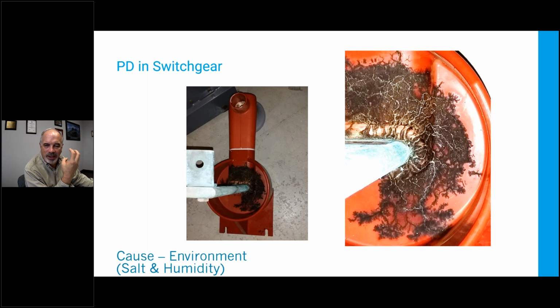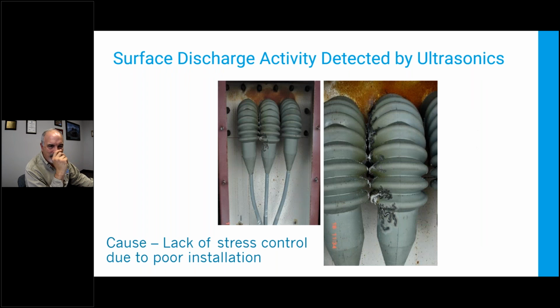That is due to the nitrous oxide in the air. Nitrous oxide will cause the copper to discolor. It'll cause steel to rust. If you're ever in a cabinet and all the steel bolts and nuts are rusty, and there's no evidence of water, or even weirder, you've got rust at the top of the cabinet and not at the bottom, why? You should have rust at the bottom where the water might accumulate. This is that cabinet that I was talking about.